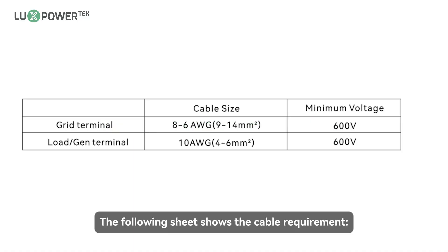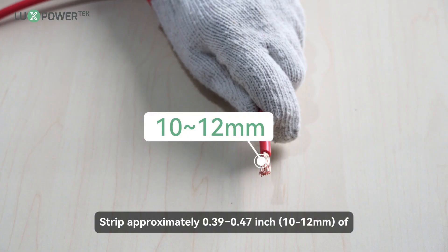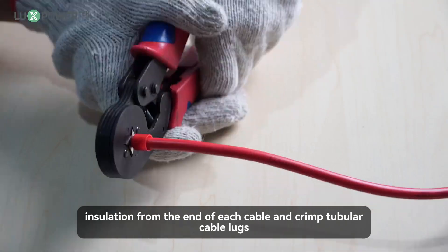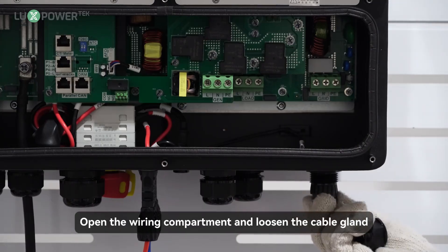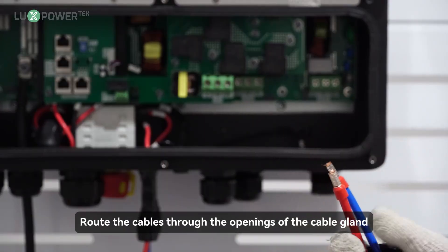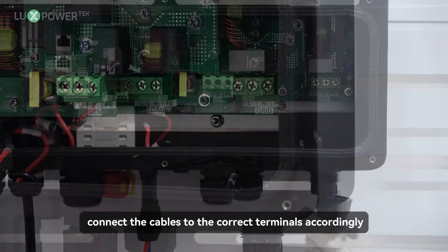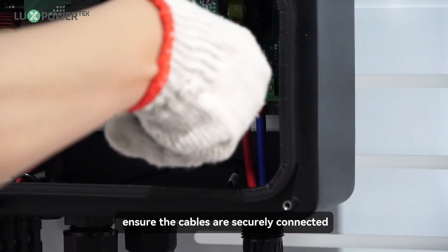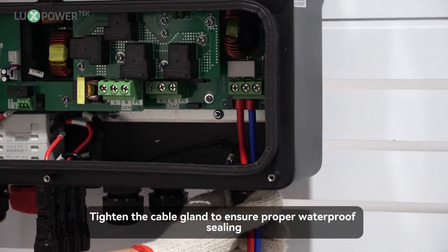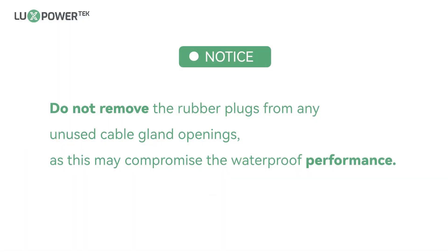The following sheet shows the cable requirements. Step 1: Strip approximately 0.39 to 0.47 inch of insulation from the end of each cable and crimp tubular cable lugs. Step 2: Open the wiring compartment and loosen the cable gland. Route the cables through the openings of the cable gland. Step 3: Refer to the labels inside the wiring compartment and connect the cables to the correct terminals accordingly. Step 4: Tighten the screws above the terminals to ensure the cables are securely connected. Step 5: Tighten the cable gland to ensure proper waterproof sealing. Note: do not remove the rubber plugs from any unused cable gland openings, as this may compromise the waterproof performance.